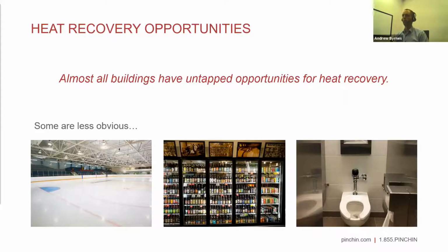Another great waste heat source that often goes overlooked is retail refrigeration and grocery stores. We've been involved with some projects that have made use of grocery store refrigeration system waste heat recovery, and it's such a large and continuous base heating load that you can, through refrigeration heat recovery, provide tremendous proportions of an annual building heating energy load. If thoughtfully designed and included, it can be a very effective way of reducing natural gas consumption in buildings and promoting heat recovery.